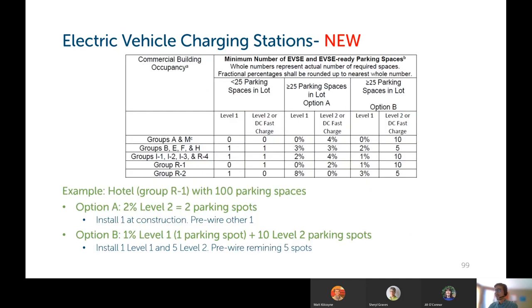So in the code, this is the new table showing how many parking spaces, how many charging stations you would need based on the size of your parking lot and occupancy type of your building. So I think the easiest way to go through this is, up here you've got any parking lot with less than 25 spaces. You find your building occupancy here, and the number of Level 1, Level 2, or DC fast charge stations you would total need to have.